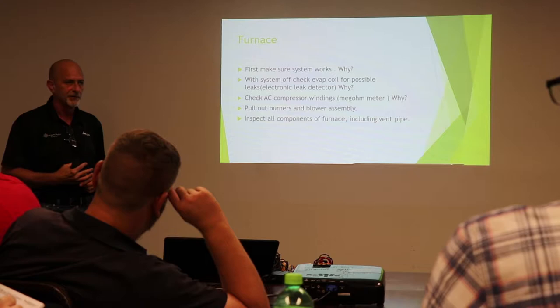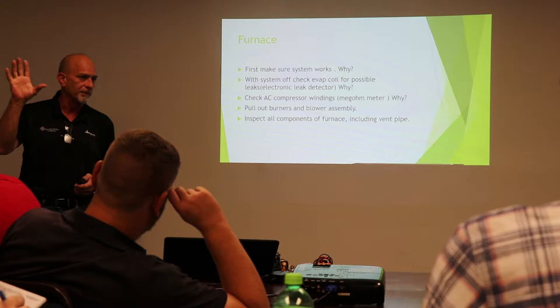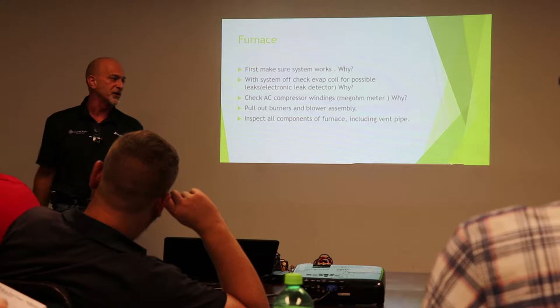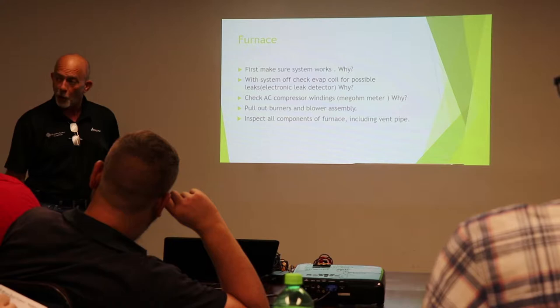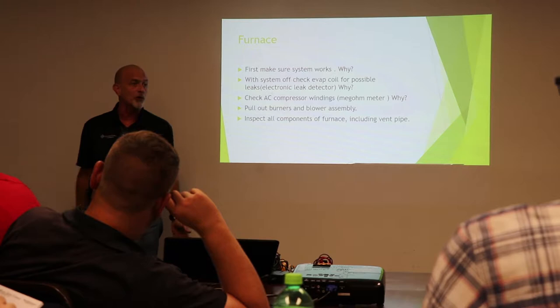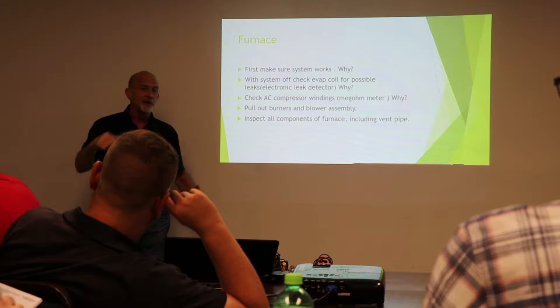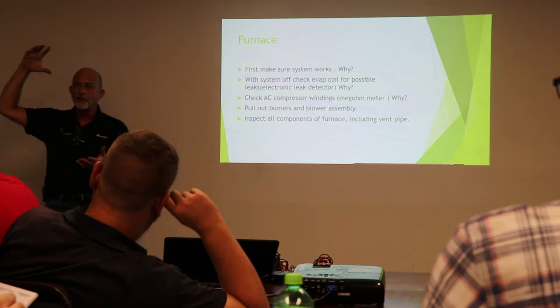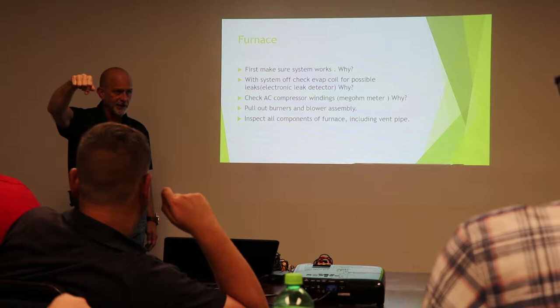How many guys carry electronic leak detectors for checking air conditioners? A lot of people, right? We can check the evaporator coil. Maybe the air conditioner wasn't that old. Maybe the air conditioner was only 7 years old. Compressor windings were good. We all know, though, if we got a copper coil that's about 7 years old, most likely it might have a leak in it, because we had a lot of leaky copper coils years ago. So we take our electronic leak detector. We can stick it in our ductwork. If you got a humidifier there, all the better, right? We can pop that humidifier off, we've got a big hole, we can stick our wand in there. Now if we have a leak, our leak detector does what? Beep, beep, beep, beep, beep. Gets louder, right?